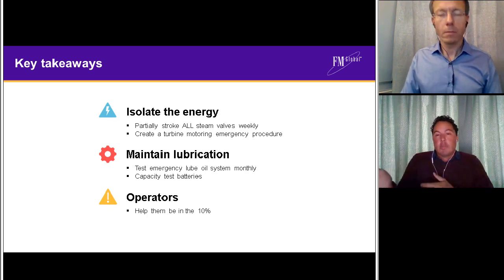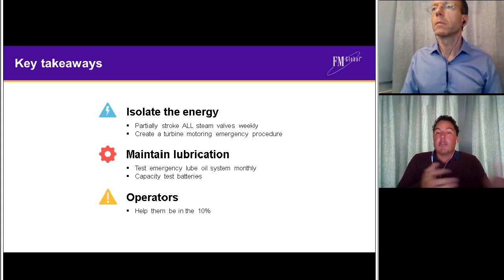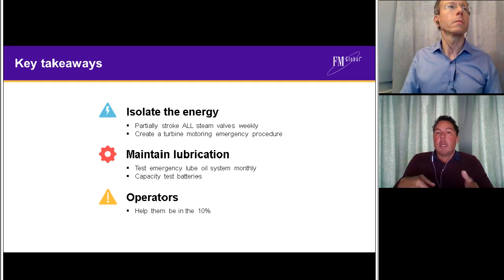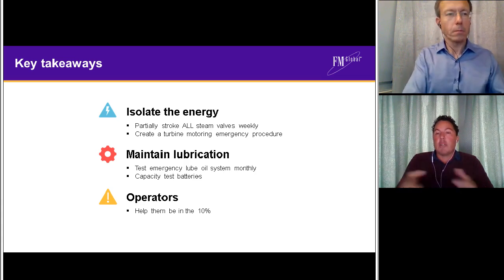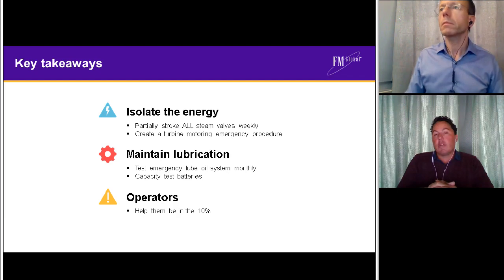On electronic overspeed, we also recommend an annual basis and when coming back from major overhaul. But again, as discussed previously, the benefit of electronic overspeed systems by and large is that you can reduce the set point and test your overspeed protection without physically overspeeding the device. So you're not shortening the life of the machine.